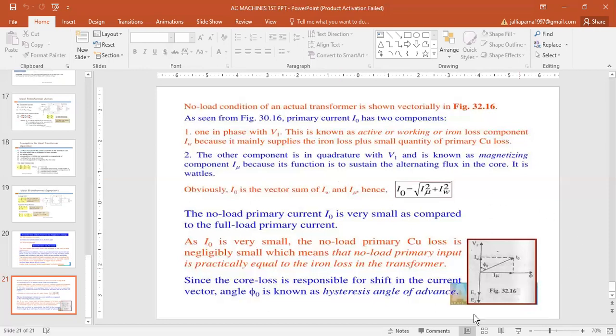So this is the vector diagram of a no load transformer. The x-axis represents flux and the y-axis represents voltage, and there is a no load current I naught, in phase with the magnetizing current, in phase with the flux. IW is the working component or active iron component, in phase with the supply voltage V1. This is the vector diagram. E1 and E2 are equal. There is the no load condition of an actual transformer.